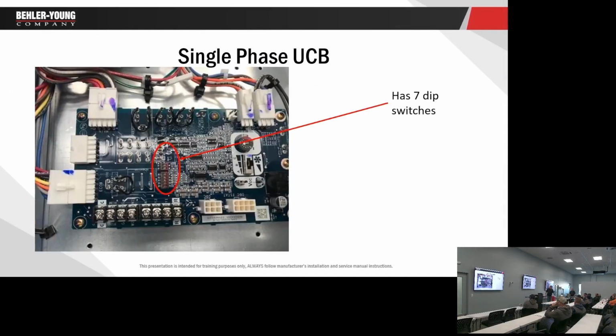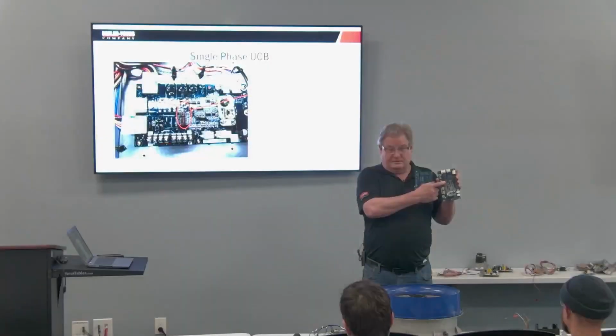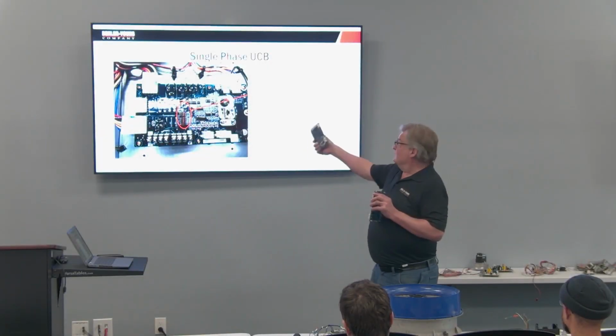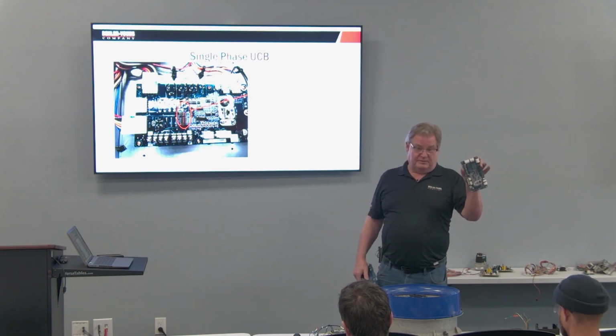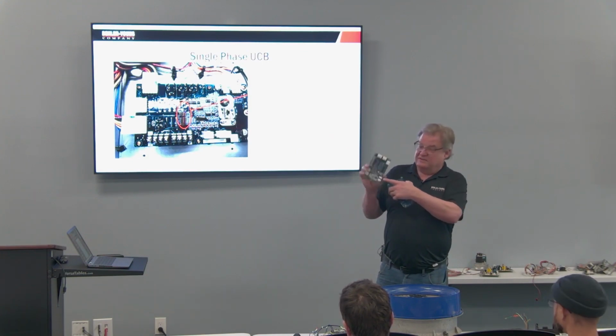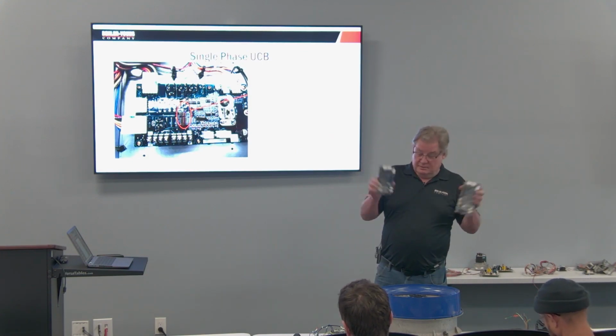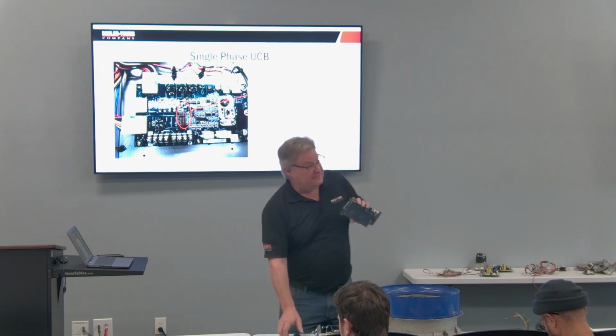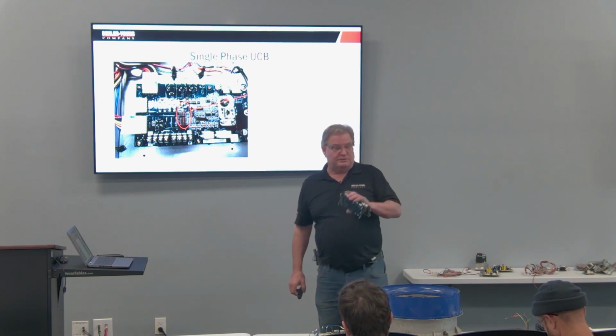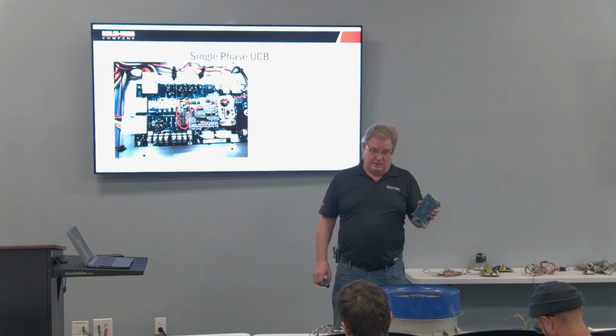Okay. So out of these two boards, there's a single-phase board and there's a three-phase board. The difference is the dip switches. The single-phase board you see up there has 7 dip switches on it. The three-phase board only has 2. If you replace the board, we need to put the dip switches back to where they were.